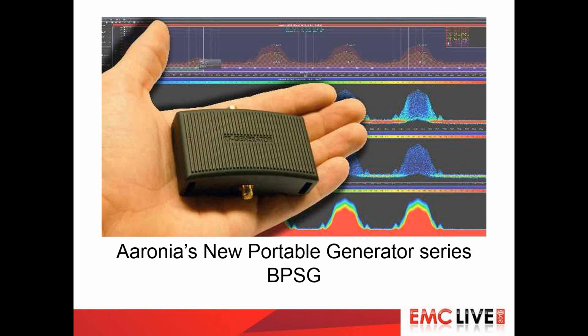The output of this thing has about a 78-80 dB range. You can go from minus 60 dBm to plus 18 dBm. It has a 4-hour battery life, and it can run off a 12-volt battery, like a car battery if need be. You can do AM, FM, and pulse modulations. Its frequency accuracy is plus or minus 1 hertz below 600 megahertz, and plus or minus 20 hertz above that, which is remarkable.